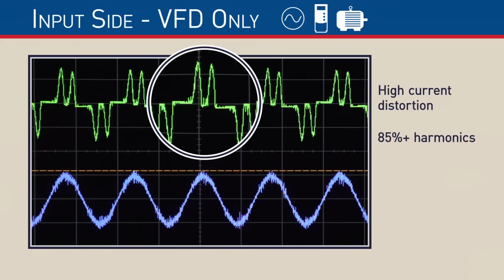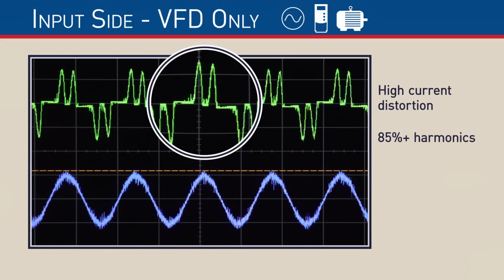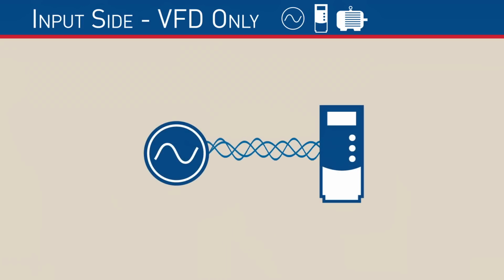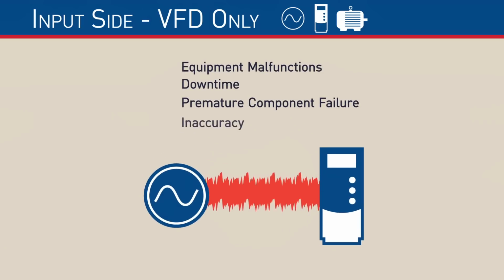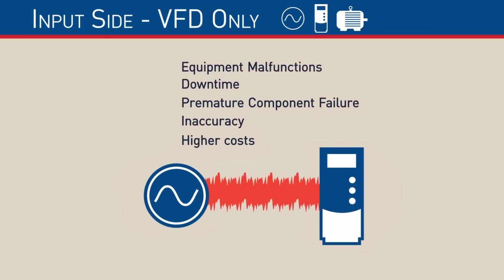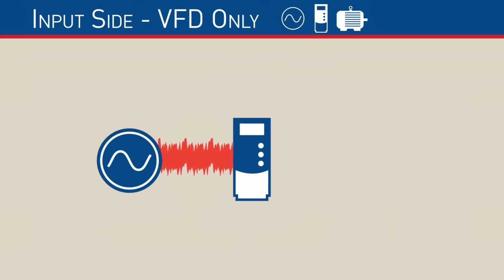A typical VFD application can contain harmonics of 85% or more. That level of harmonics is not ideal because they create alterations in the voltage waveform, which leads to unwanted problems with the connected equipment. High levels of harmonics often result in overheating and malfunctions in transformers, motors, and wiring. They can also induce nuisance tripping, inaccurate instrumentation measurements, and higher energy costs due to poor power factor.